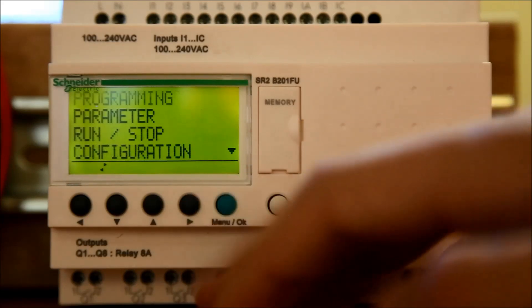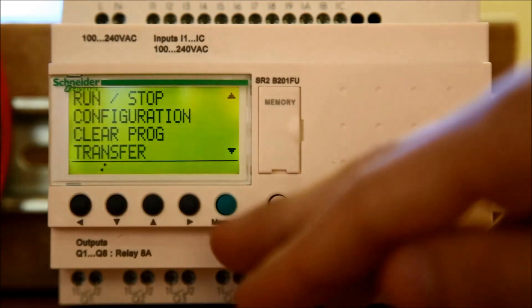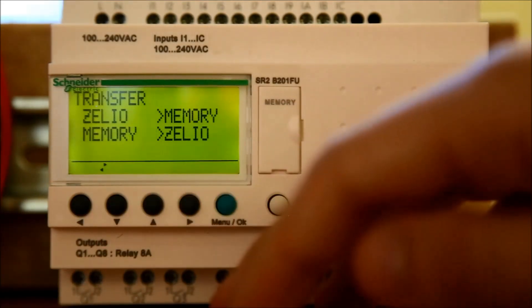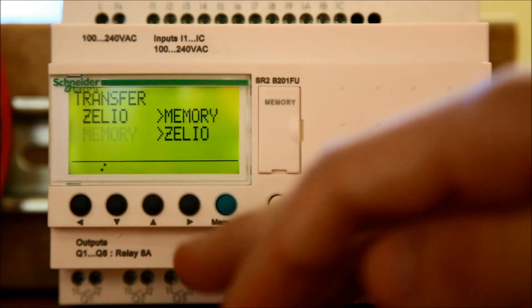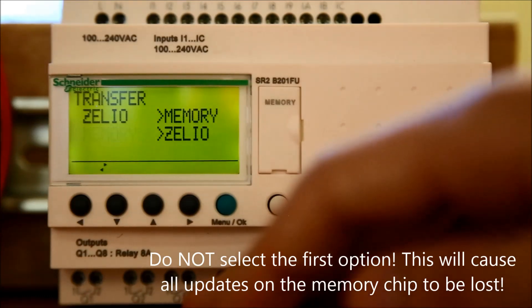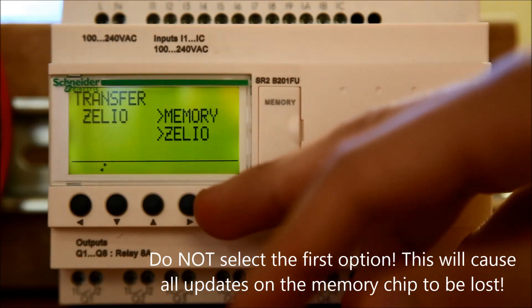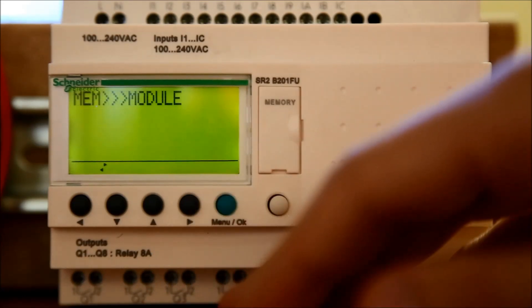Next, hit the Menu OK button and use the up and down arrows to scroll to the Transfer option. Press the Menu OK button. Use the down arrow to select Memory to Zelio to transfer the program from the memory chip to the Zelio. Press the Menu OK button. After a moment, you should see a Transfer OK confirmation screen.